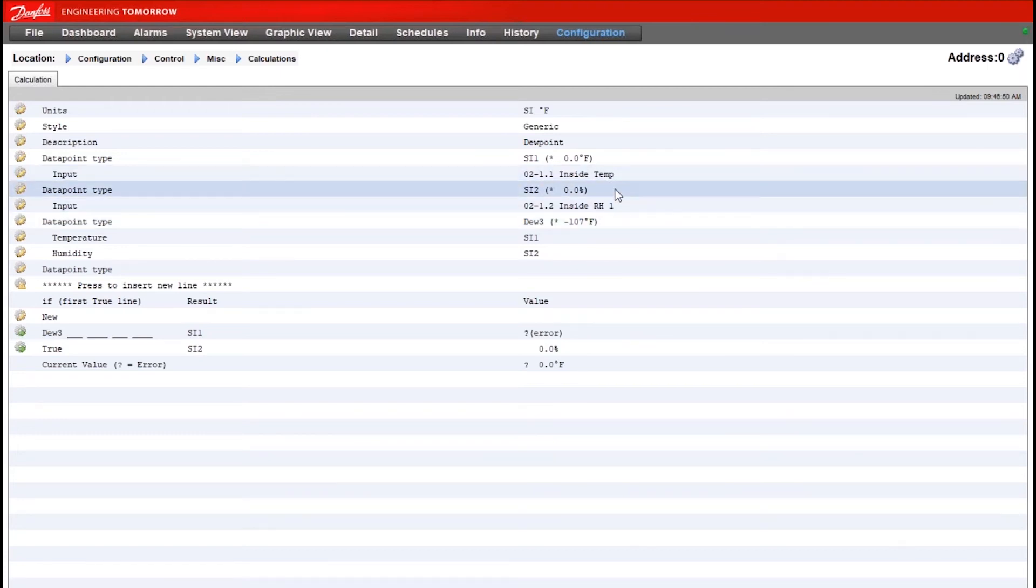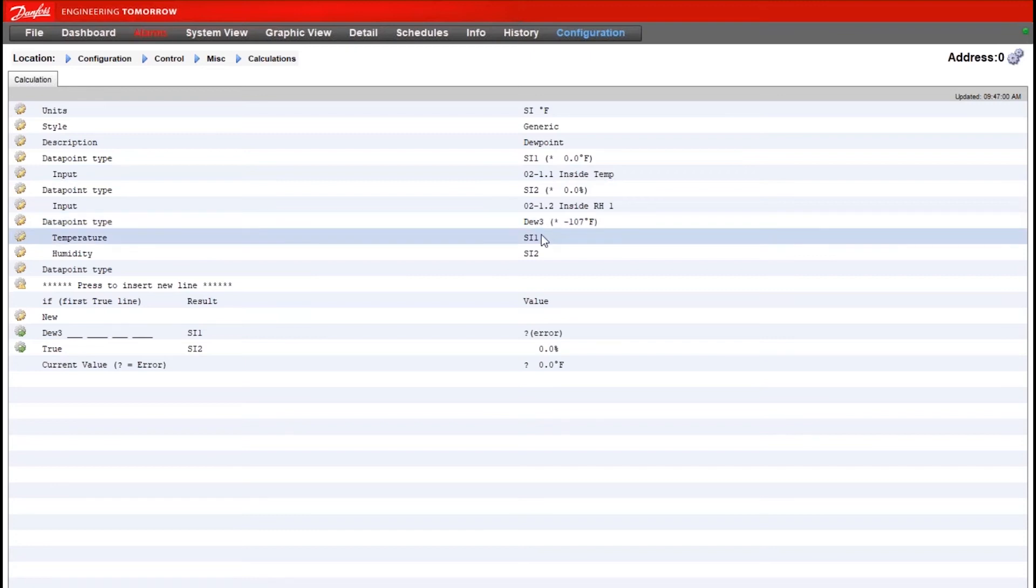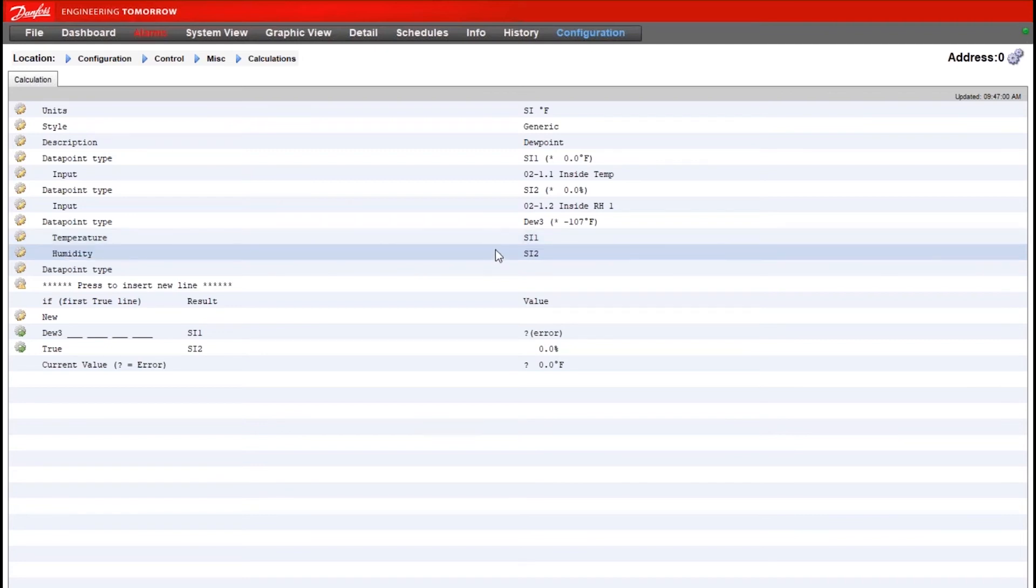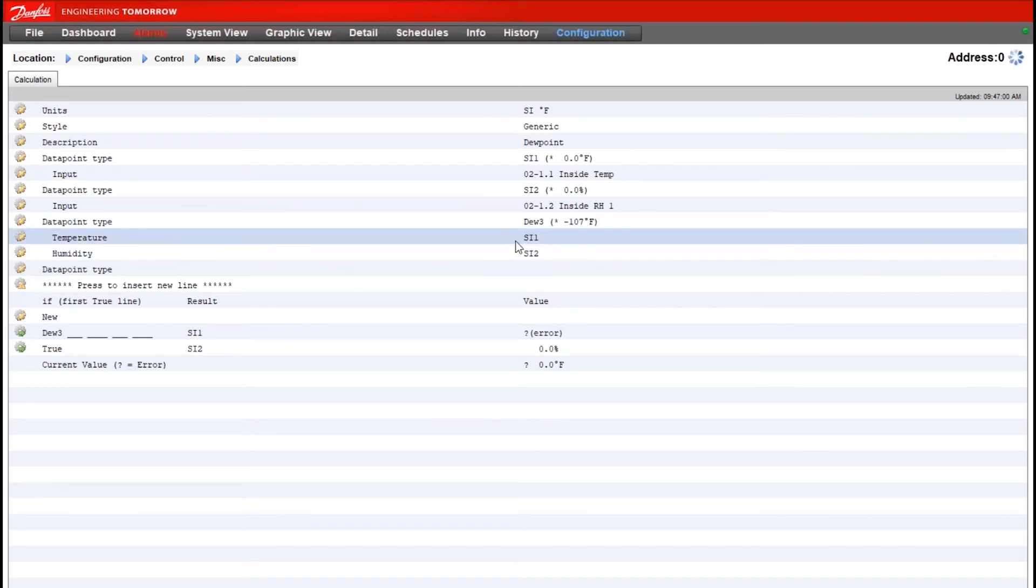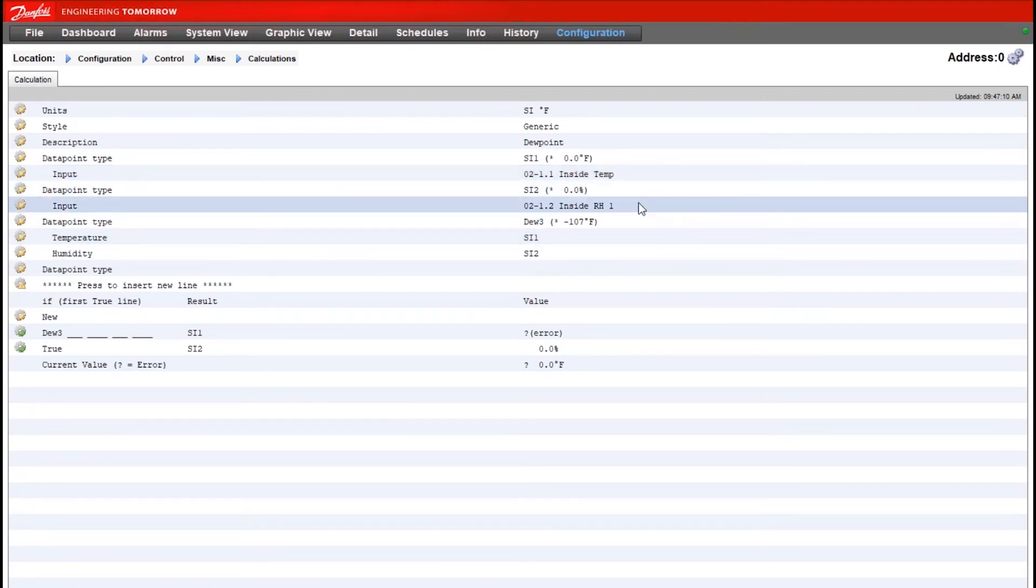Now that we have those configured, our data point type for the third input will be the dew point option, and you can see below it's already defaulted to the right options. So our temperature value will be based on SI1, which is our indoor temp sensor. Humidity will be based on SI2, which is our indoor humidity sensor.